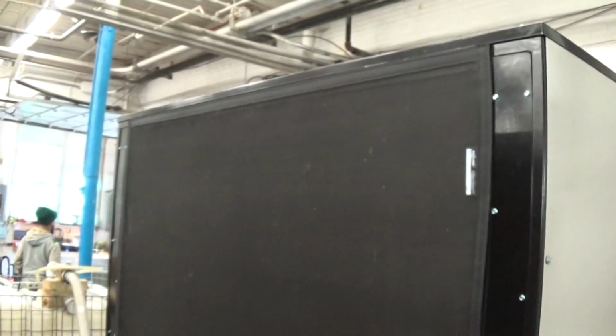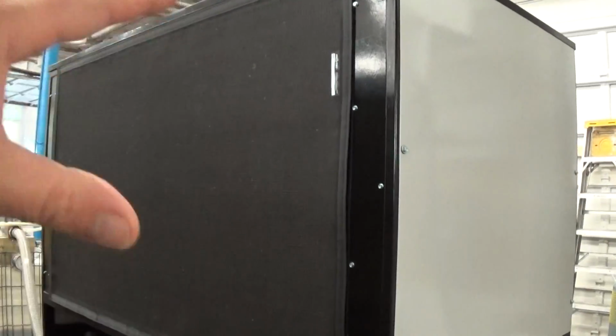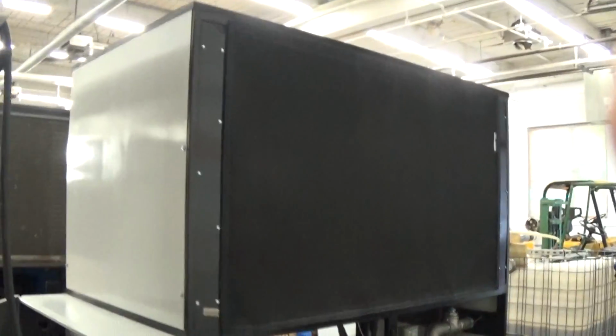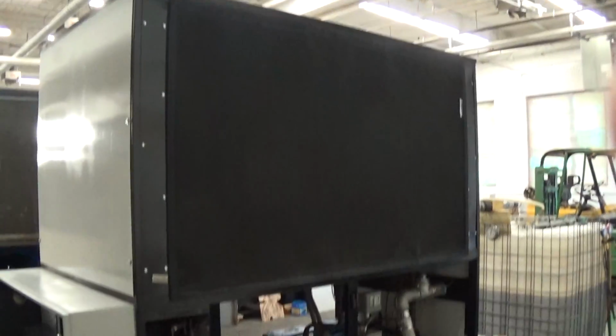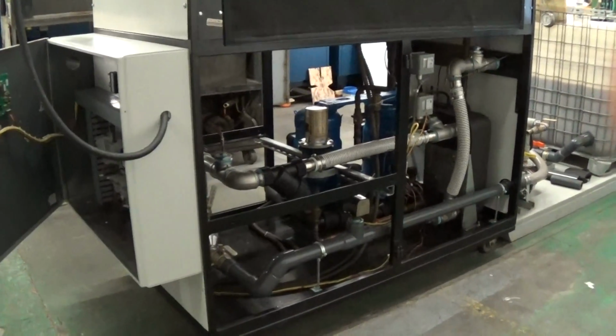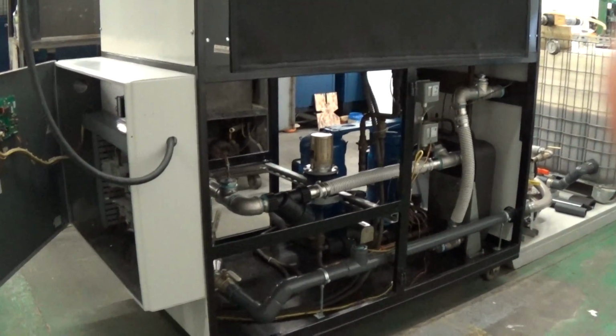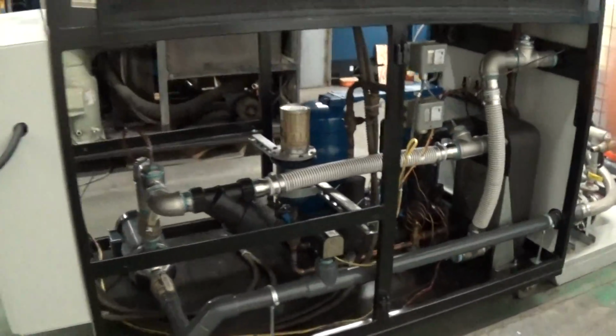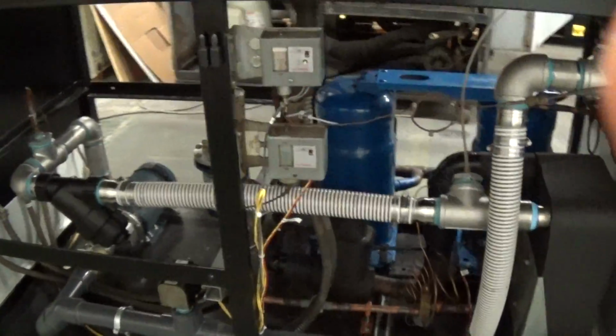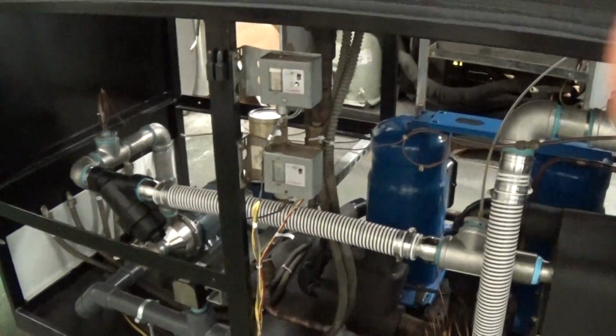What we have up above, or behind these panels here, is two squirrel cage blowers, and those are high flow. We got new belts for those, and we adjusted the motors and the belts. Those are high flow condenser fans up above, and that's suitable for ducting out of your building. It is an indoor chiller, of course, but you can put ductwork right over the top of that. That's an extra charge, extra feature the original customer purchased.